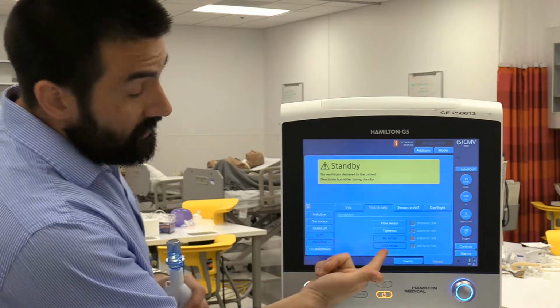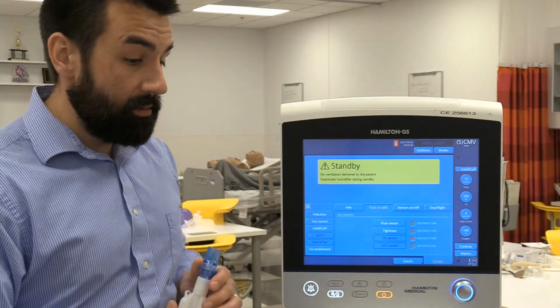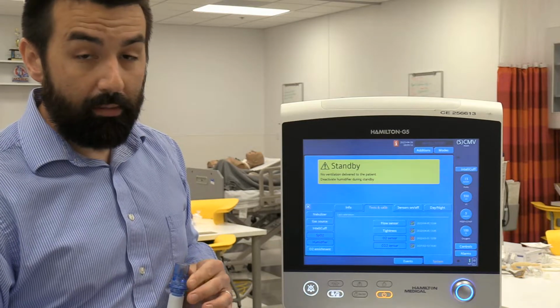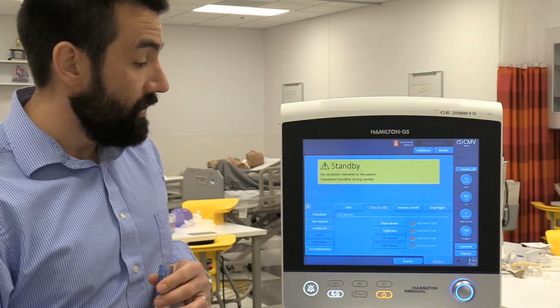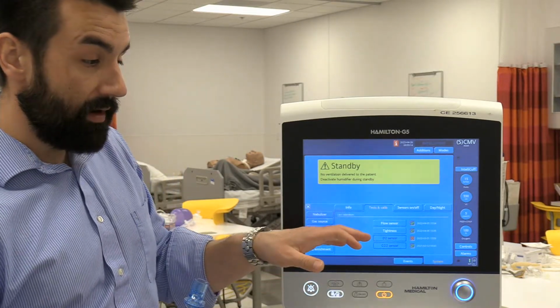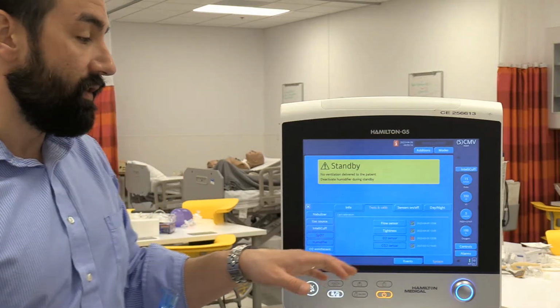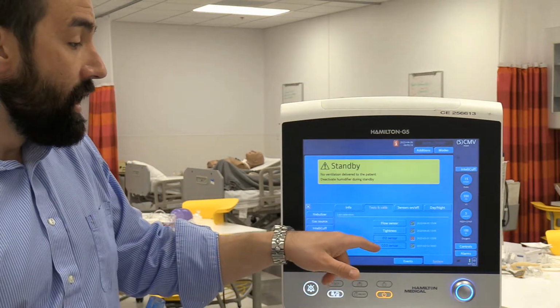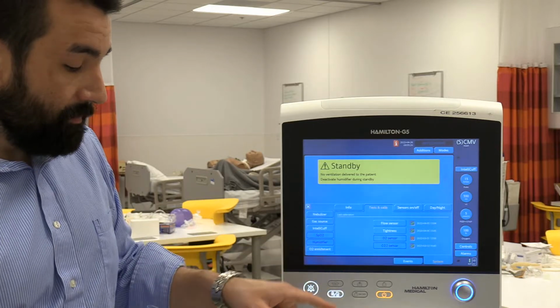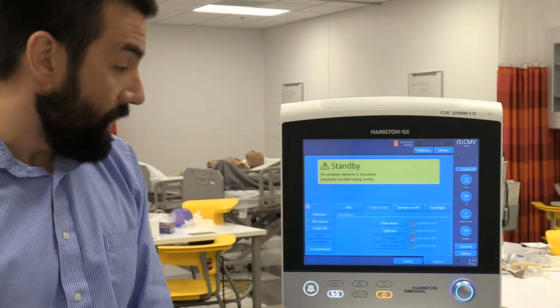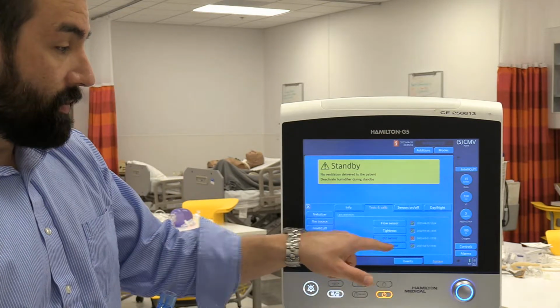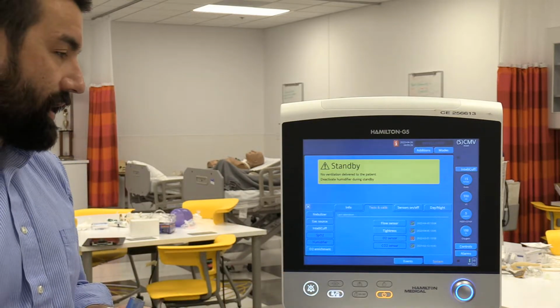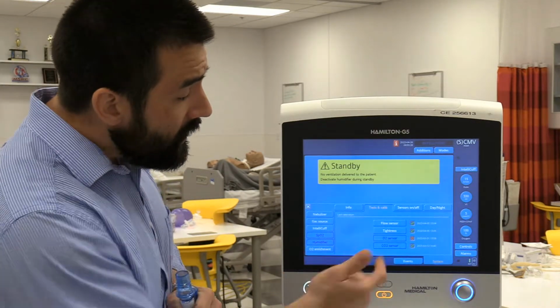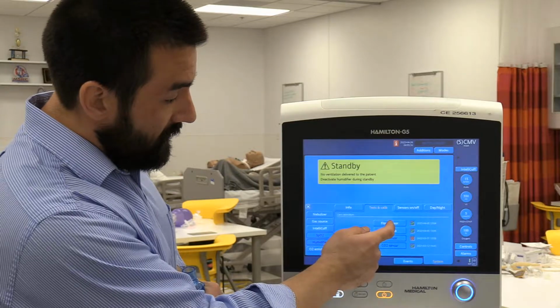All right, this vent, as well as a lot of the Hamiltons, do have built-in volumetric capnography capabilities, and very superior compared to regular sidestream capnography most of you guys are using out there. If I had this plugged in, there's a little module on the front bottom part of this ventilator. This would be lit up, and it would allow me to do that and zero it out and things like that, which I'd recommend. So right now I'm going to just walk through the flow sensor and tightness test.